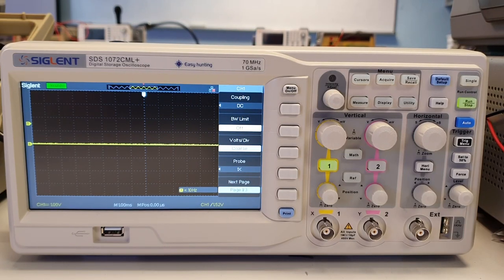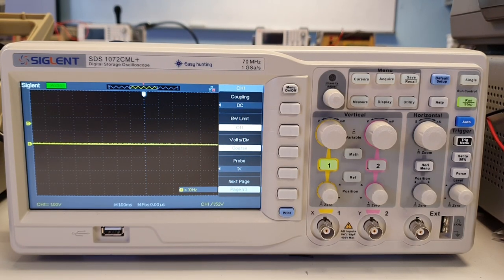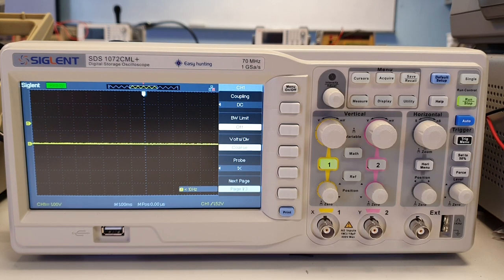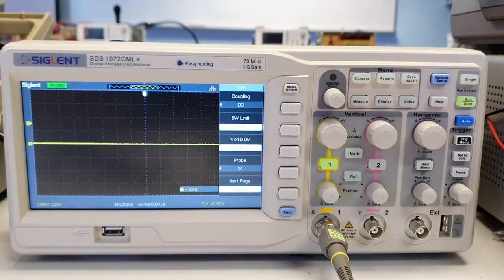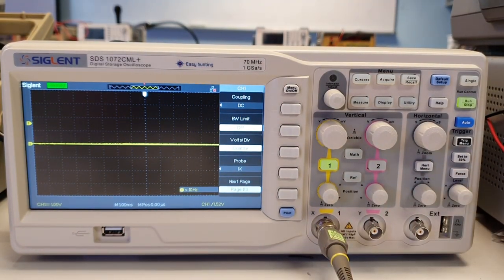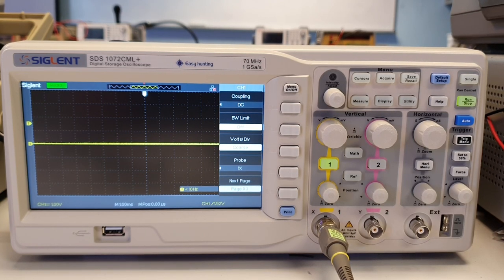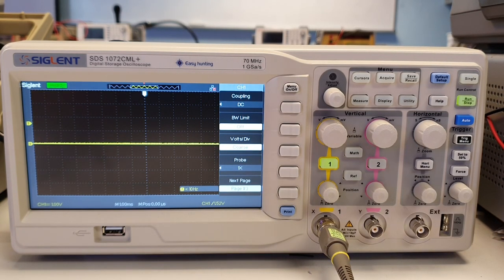Before we capture and measure any waveform on the digital oscilloscope, there is a need to perform calibration of the oscilloscope channels. We need to connect the BNC side of the scope cable into one of the channels like this. Before we hook the scope probe onto the calibration ring, ensure the probe multiplier is set to ×1.